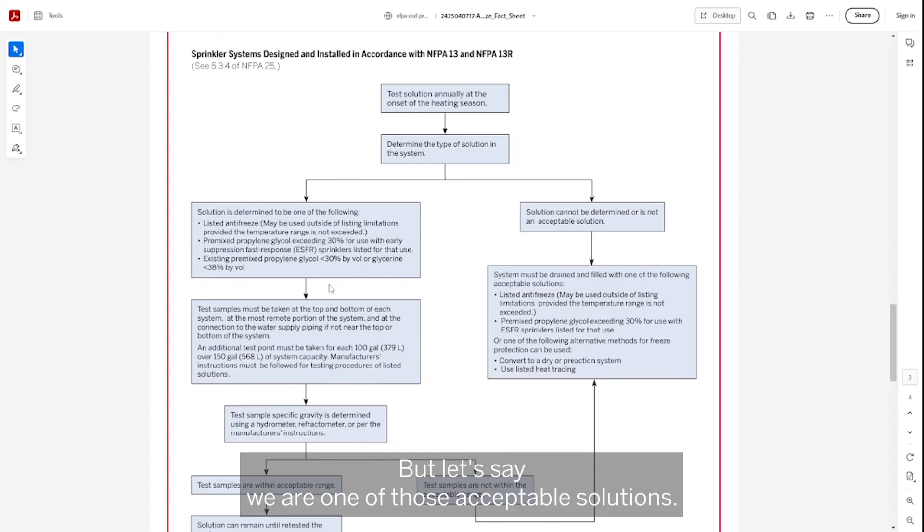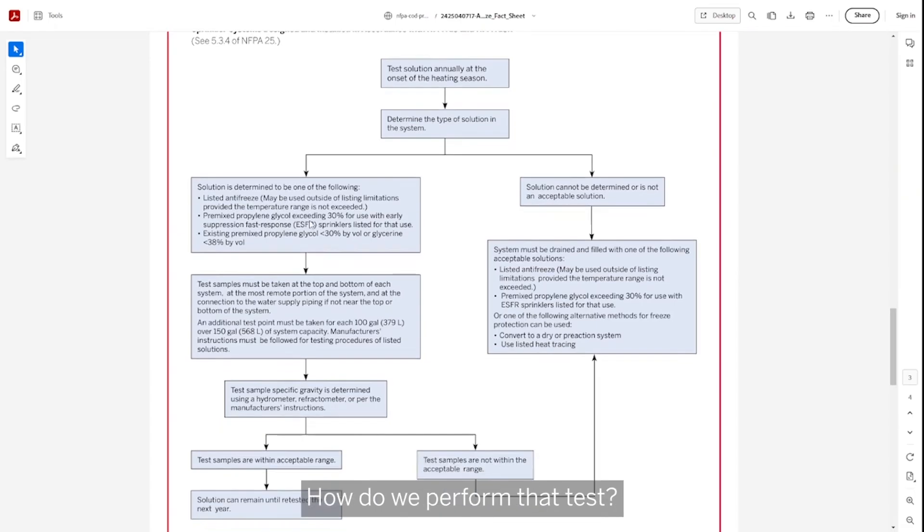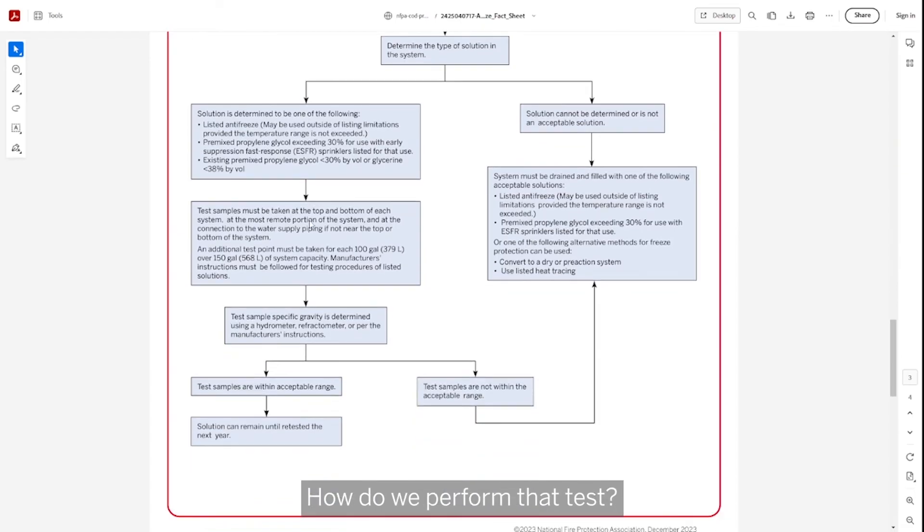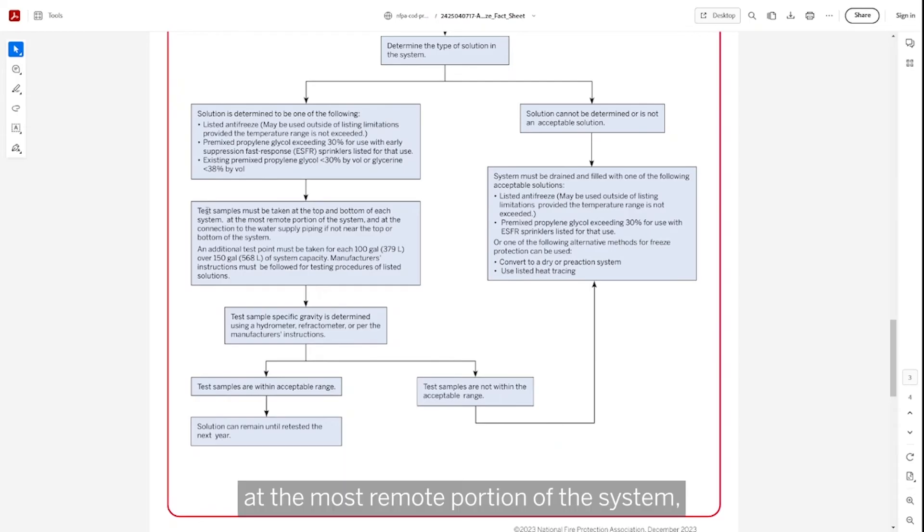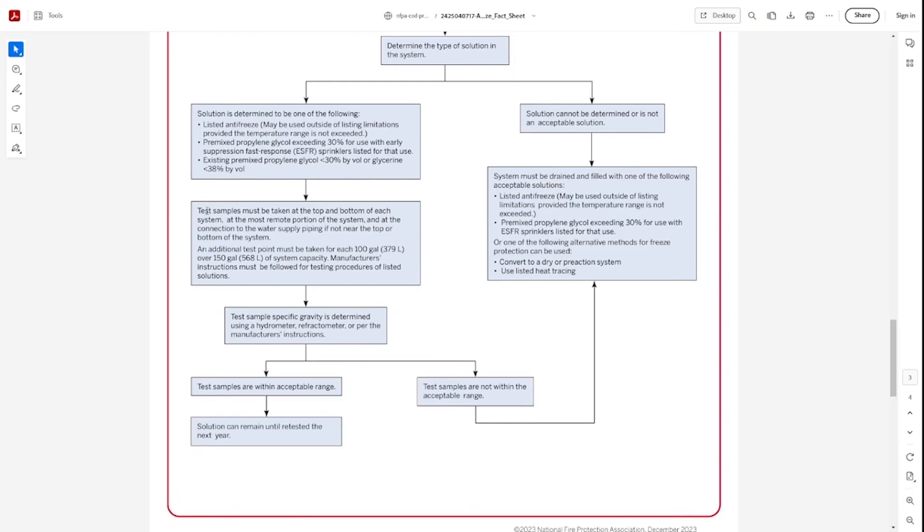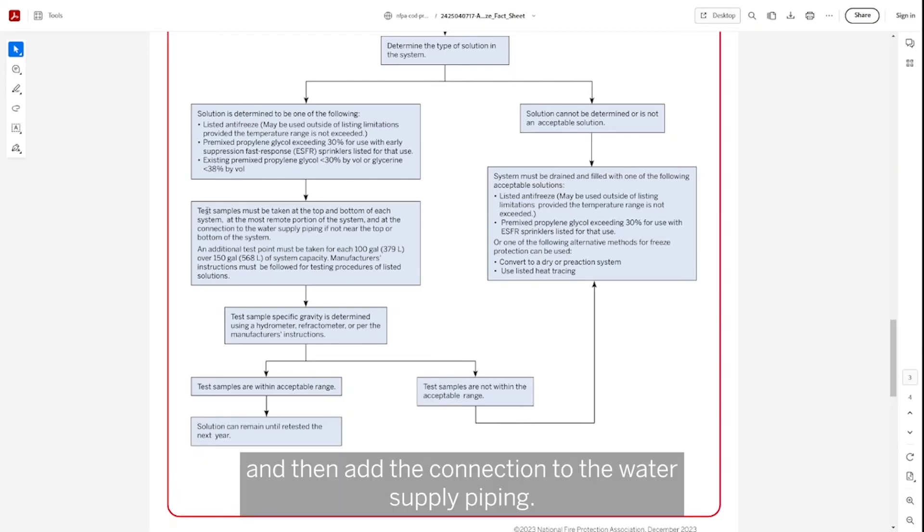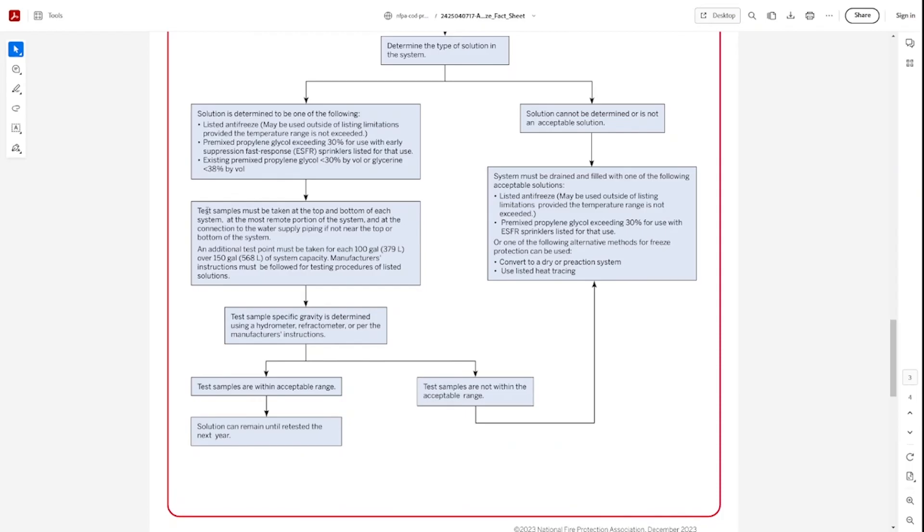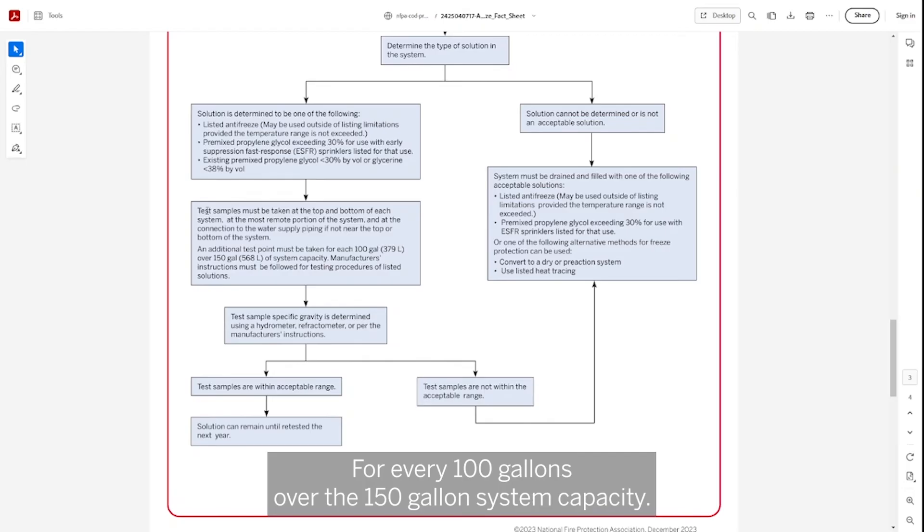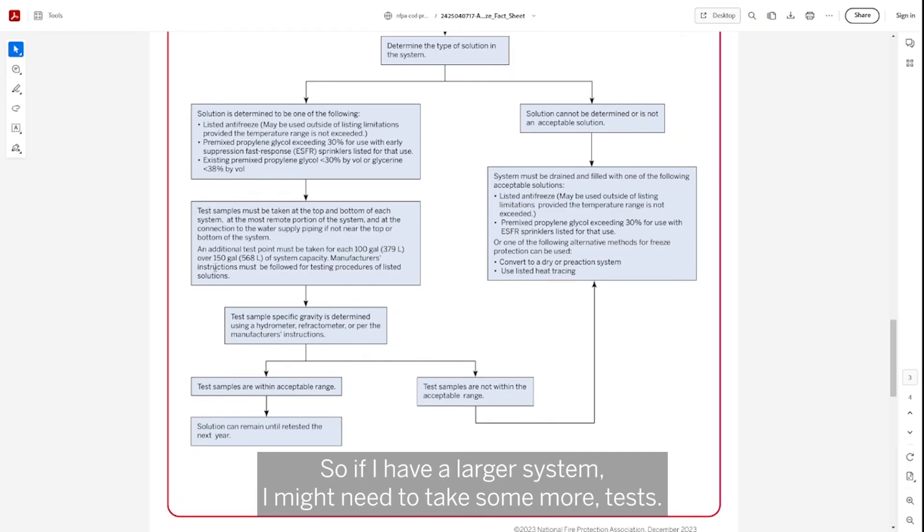Well, let's say we are one of those acceptable solutions. How do we perform that test? We're going to take a test sample at the top and bottom of each system, at the most remote portion of the system, and then at the connection to the water supply piping if that's not near the top or the bottom of the system. Then I need to take an additional test point for every hundred gallons over the 150 gallon system capacity. So if I have a larger system, I might need to take some more tests.